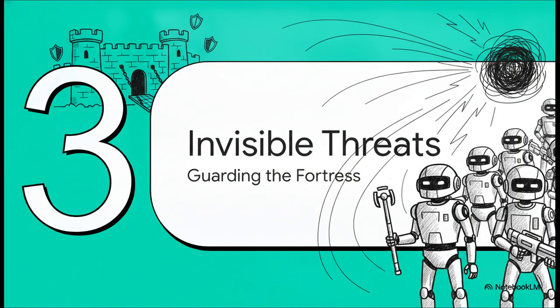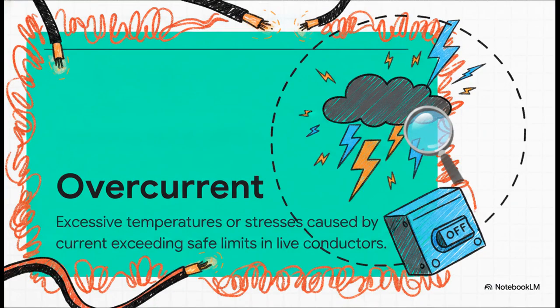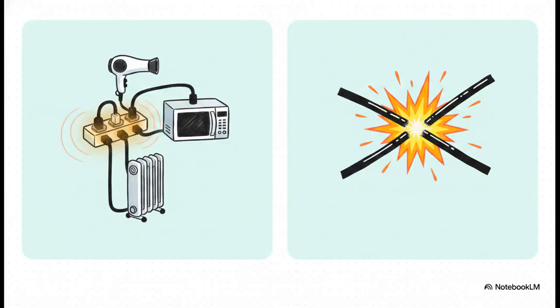Which brings us to part 3, protection against invisible threats. In this section, we deploy the guards, and the primary invisible threat these fortress guards are constantly scanning for is called overcurrent. This happens when the current exceeds the safe limits of the live conductors, which causes excessive temperatures or electromechanical stresses. To put it simply, it's the threat of melting wires and starting fires. Protective devices have to automatically sever the supply before this overcurrent can reach a dangerous magnitude. Now, what's really interesting about this slide is how the standard breaks overcurrent down into 2 very distinct enemies.